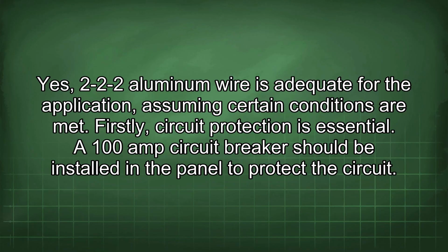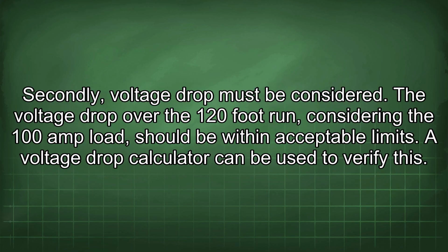Yes, 2-2-2 aluminum wire is adequate for the application, assuming certain conditions are met. Firstly, circuit protection is essential. A 100 amp circuit breaker should be installed in the panel to protect the circuit. Secondly, voltage drop must be considered. The voltage drop over the 120-foot run, considering the 100 amp load, should be within acceptable limits. A voltage drop calculator can be used to verify this.